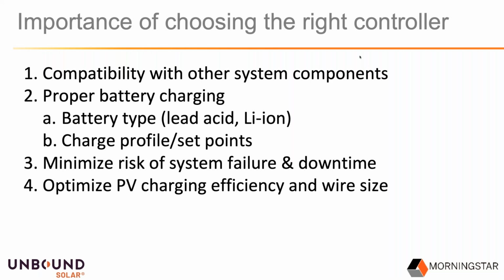This is pretty obvious, especially if the site is in a remote location or if replacing components is difficult or expensive. And then number four, we want to optimize the PV charging efficiency and wire size. By selecting the right controller, you can make sure that you're not buying oversized wire or needlessly buying large wire when we could use a different controller and a different design to better optimize that. So that's why it's important.